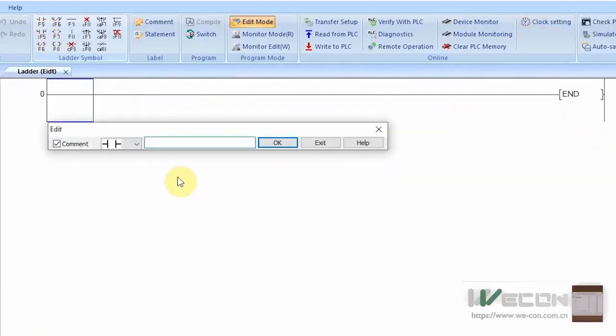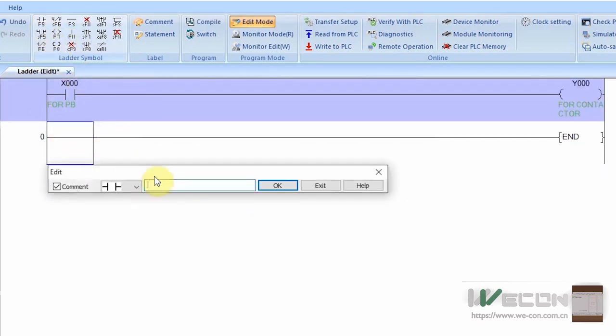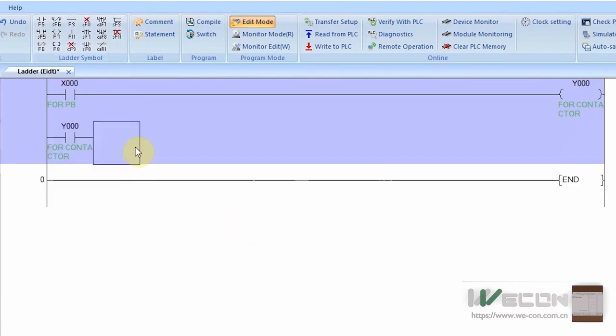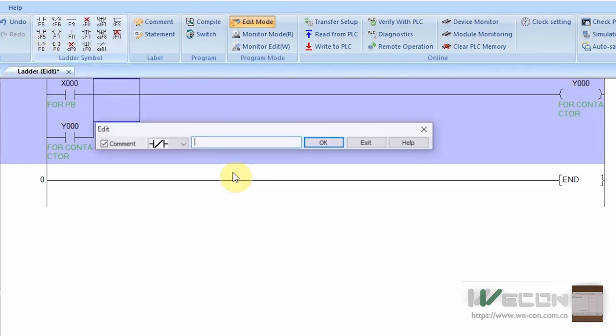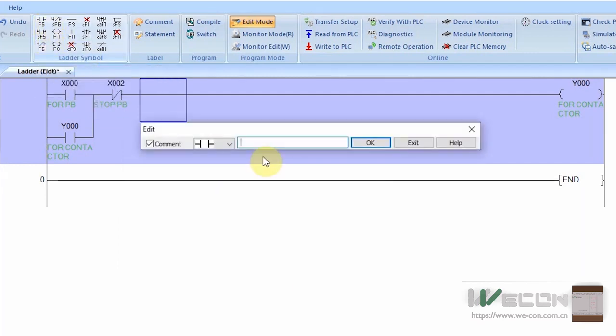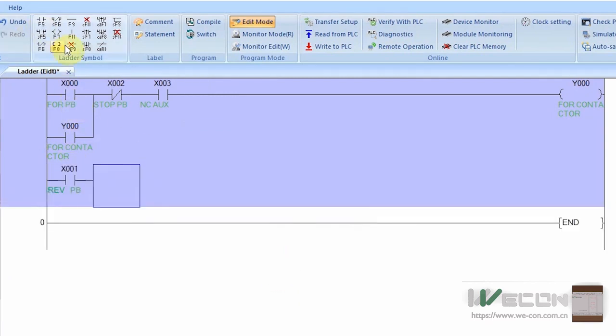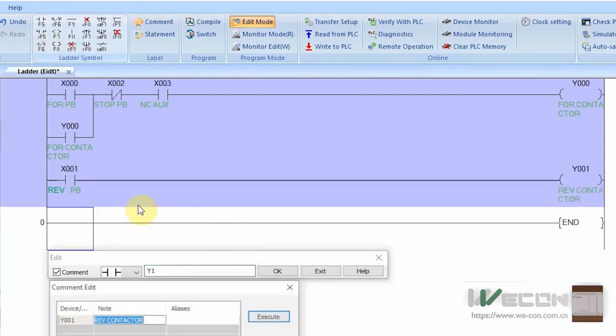Now let's look at the programming part of the PLC. First, we take a normally open contact of the start pushbutton X0, which will turn on output coil Y0 for the forward contactor. We put a normally open contact of output Y0 in parallel with X0 so that pressing X0 once latches on output coil Y0. To turn off the output, we add a normally closed contact of the stop pushbutton X2. For safety, we also add a normally open contact of the motor protector auxiliary NC contact at X3 — if the motor is overloaded, this contact will open and unlatch output coil Y0. The same logic is used to run the motor in reverse using reverse start pushbutton X1 and Y1 reverse contactor.